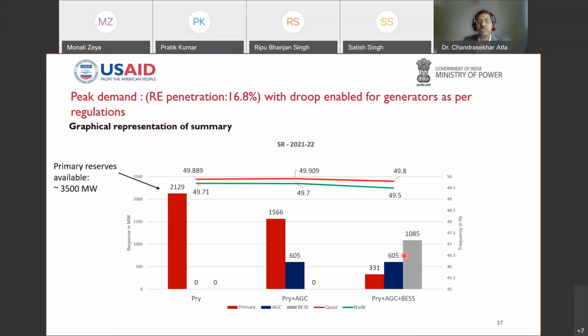So if we use the battery dispatch of 1085 and the secondary reserve 605, we only require 331 megawatt from the conventional units. So here the major thing is the battery is providing the inertial and primary reserves. Hence, if you take the direct calculation, around 3,500, you don't keep anything, 3,500 you can use for other purposes, and then only use 331. So approximately 3,000 megawatt can be released for other things, and the battery can be deployed into the primary. So that's the way the study we have made.